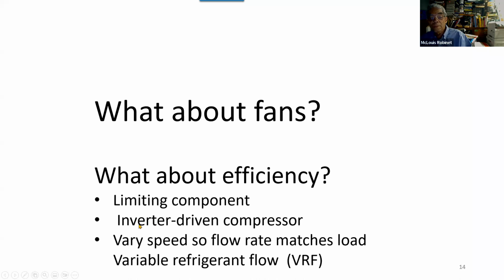To do that, we use what's called an inverter. So we have an inverter-driven compressor, and what it essentially does is exactly match the amount of refrigerant that goes through that expansion valve to the demand. Using an inverter-driven compressor enables us to vary the amount of refrigerant flow. Any system in which you can change the speed of the compressor to match the amount of refrigerant you need is called variable refrigerant flow, or VRF. So that's the new buzzword. It's new and popular in the United States, but it actually started in Japan almost 30 years ago.